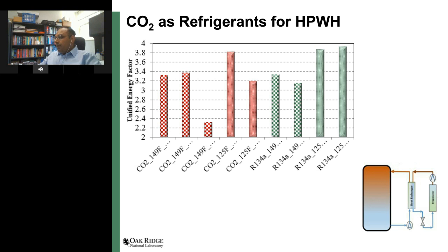Again, in this case, if you're using additional infrastructure, the variable speed pump as well as a gas cooler, it is going to cost more, and it will have its own issues because of the higher cost. Regardless, one of the major problems with the CO2 system, as I elaborated earlier, is the higher operating pressure. As compared to 300, maybe 400 psi, we are operating at about 1100 psi for the CO2 systems, and much stronger infrastructure is required to contain the refrigerant within the system.